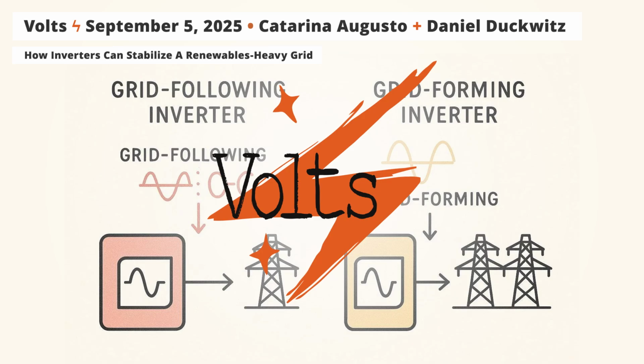And you're right, there is. In the seconds or milliseconds between when demand rises or falls on a grid and a grid operator is able to respond by adding or subtracting supply, the energy to buffer that transition and keep frequency and voltage under control is provided by inertia.